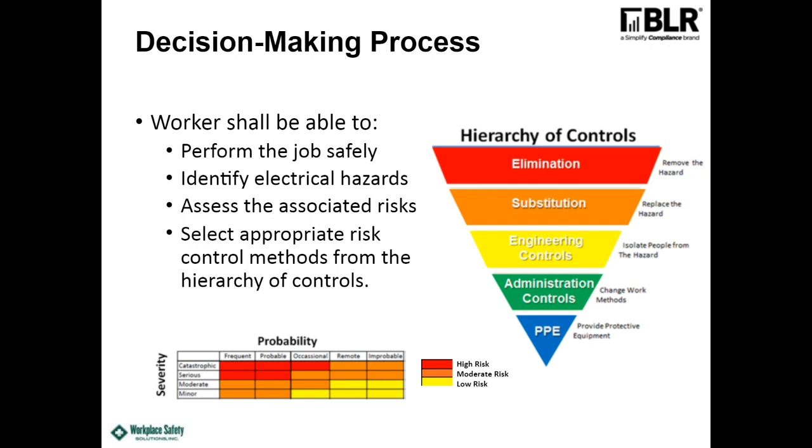Well, it depends on a lot of things. How new is it? Has it been maintained properly? What kind of mechanism is it? In one case I worked it was under salt water for a while during Hurricane Sandy. Well, that's going to increase the likelihood of a problem in a big way. So I'd probably be in the red high risk level with something like that. So then you just step up your protection one level, just to give yourself a little extra protection. And if it's too high, then you just have to go with elimination or one of the others above and not rely on PPE. You have to try to shut it down if you can.